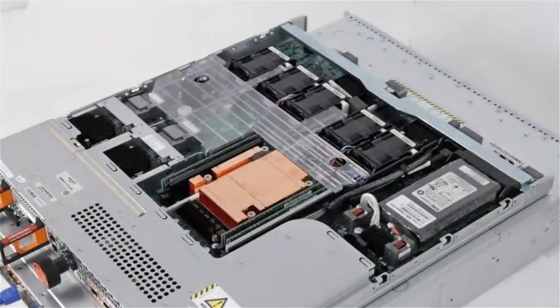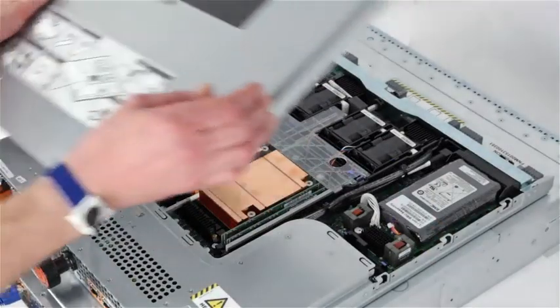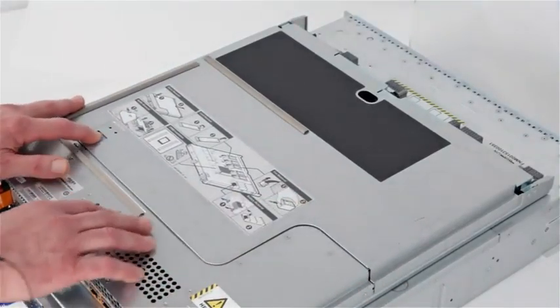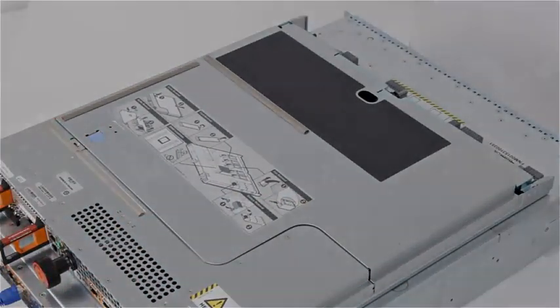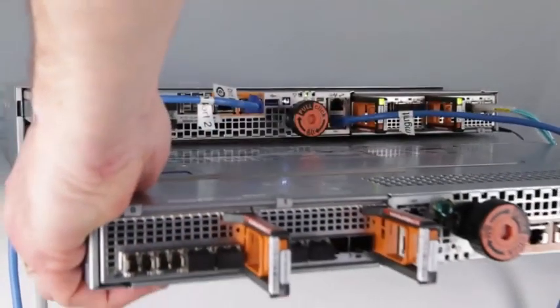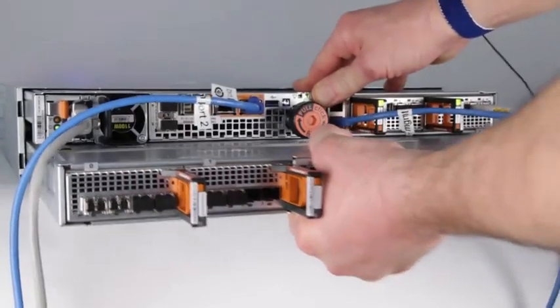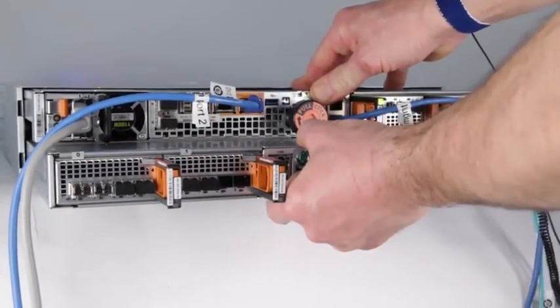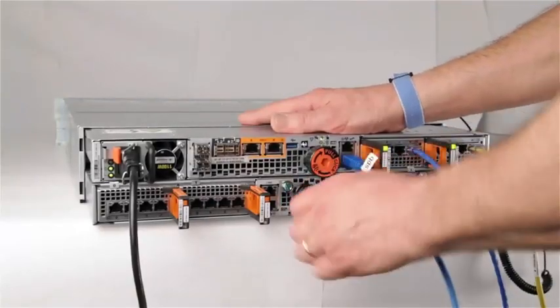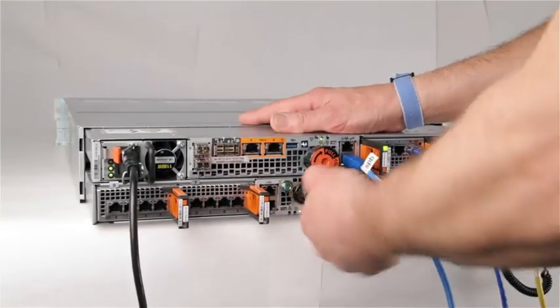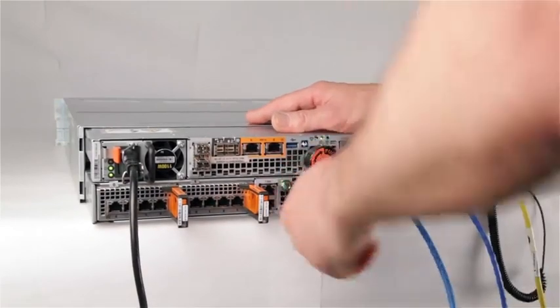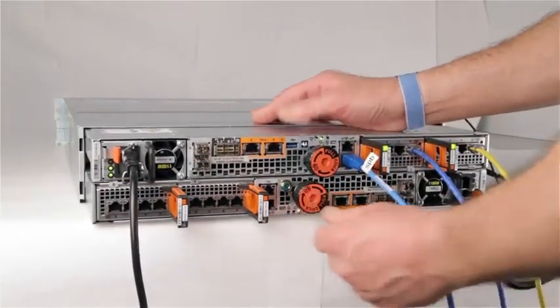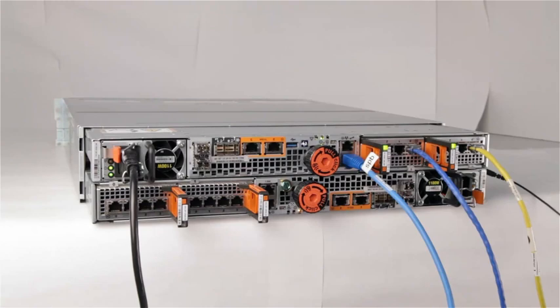Position the top cover over the SP assembly and align it with the slots in the sides at the rear of the assembly. Pull the top cover forward approximately one-half inch to secure it in place. Align the SP assembly with the enclosure slot and slide it into the slot until it stops. Turn the orange torque limit screw handle clockwise until you hear a click sound from the handle. The click sound indicates the torque limit is reached and the SP assembly is seated fully in the enclosure. Push the orange torque limit screw handle into the SP assembly until you hear a click again. The click indicates the screw handle is secured in the assembly.